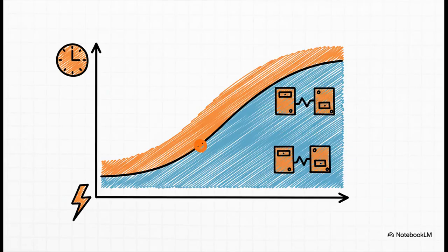And we can see this whole relationship on a graph, which we call a time-current characteristic curve, or a TCC curve. It's pretty simple. You've got time going up on the vertical axis and current going across on the horizontal. Any fault that lands up in that relay operating region, meaning it hits a certain current level for a certain amount of time, is going to trigger that device to trip.